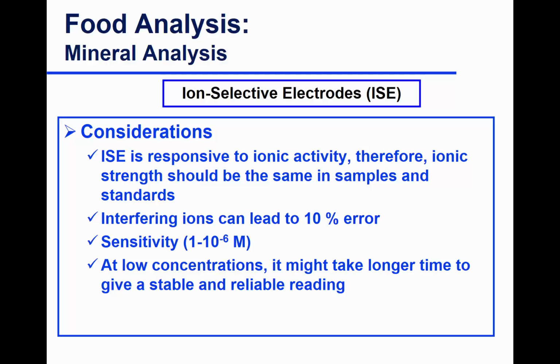So the ion-selective electrodes are responsive to the activity of the ions. So if you use standards to quantify, you want to make sure your standards have similar ionic strength to your samples. Otherwise, you will have interferences and wrong results.